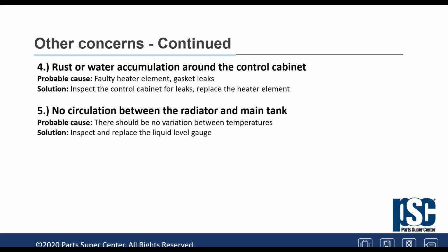Again, we spoke about the rust and water accumulating. Here we go. A control cabinet usually has what we call a space heater. What this does is prevent condensation in the control cabinet, and sometimes for some reason it gets turned off, and now we start having some funny things happening. Condensation in summertime gets very hot, with humidity and so forth. The heater has the purpose of limiting those factors, and that could be the cause. If we find that the heater element is not doing its job or it's not connected, maybe we should check why.